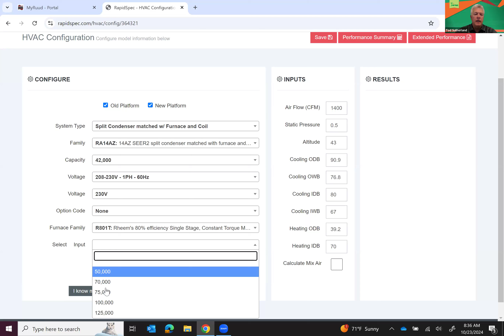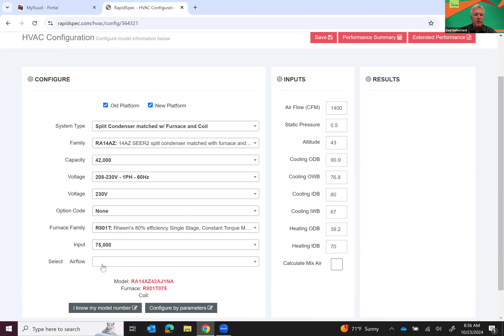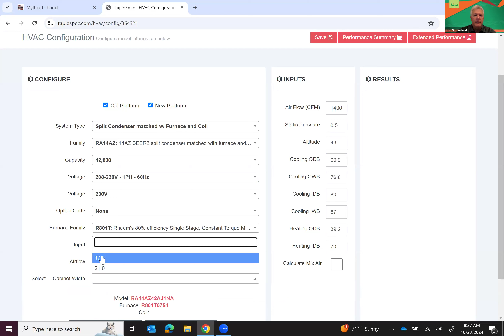Now it's asking for my input, so you've got your different input BTUs here. I'm going to select the 75,000 BTU, and I'm doing this on purpose. Airflow, I want up to 4 tons. For cabinet width, I'm going to select 17.5 because we have the tendency of wanting the narrowest cabinet, so we'll just select this 17.